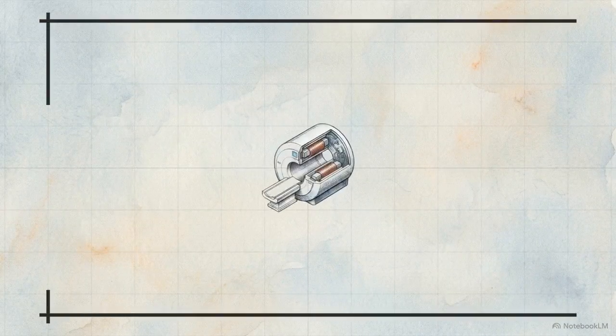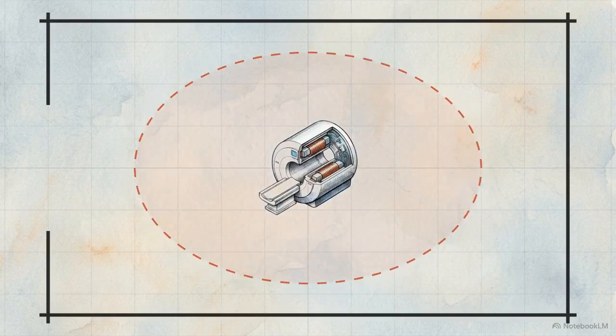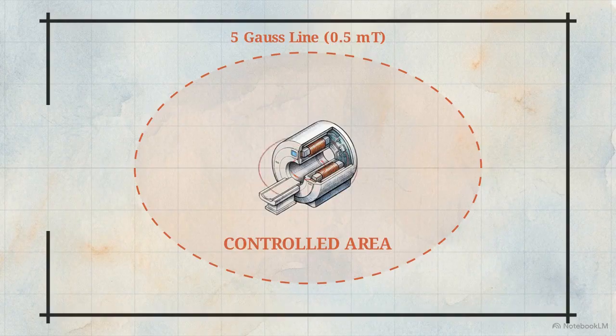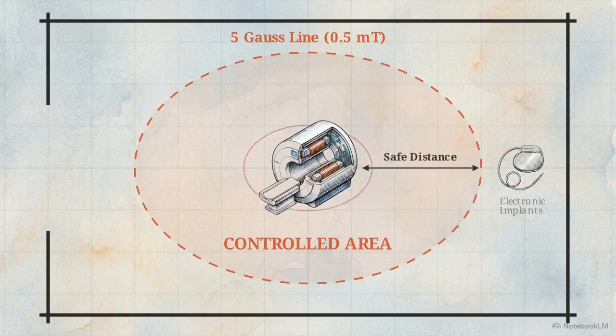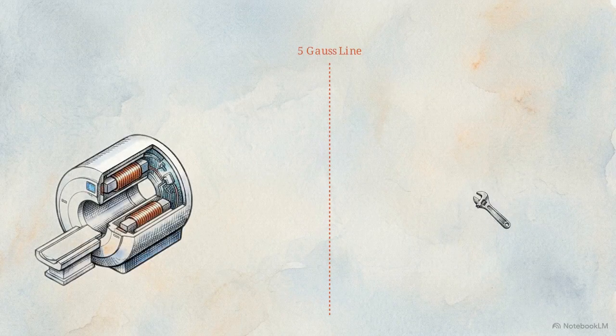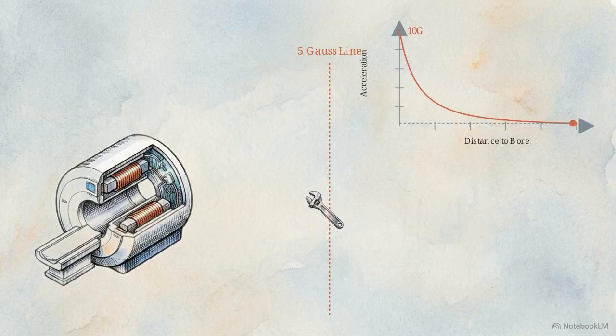This architectural layout marks the 5 Gauss line, the spatial boundary where the magnetic field becomes strong enough to interfere with electronic devices. Anyone with a contraindicating implant, like an incompatible pacemaker, is strictly excluded from crossing this threshold. Ferrous objects that cross this line undergo the ferromagnetic missile effect. As the distance to the bore decreases, acceleration increases. At the center of a 1.5 Tesla magnet, a loose object can reach speeds exceeding 80 kilometers per hour.